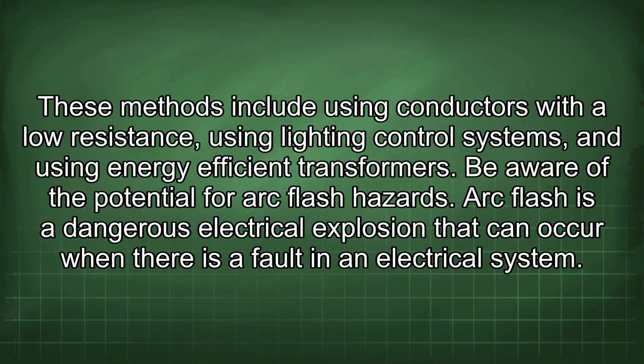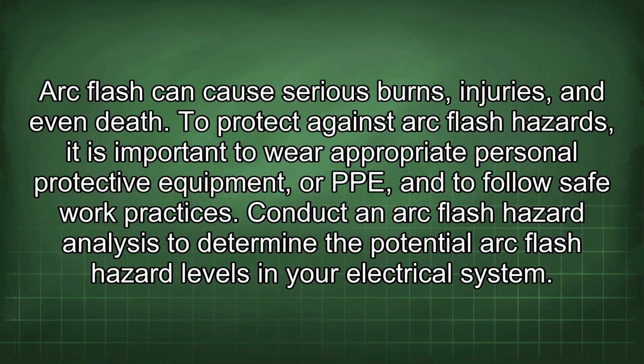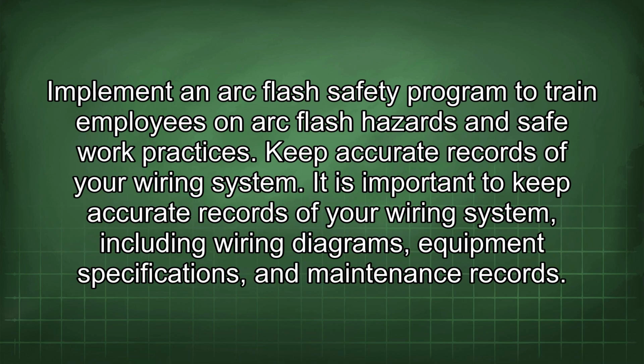Be aware of the potential for arc flash hazards. Arc flash is a dangerous electrical explosion that can occur when there is a fault in an electrical system. Arc flash can cause serious burns, injuries, and even death. To protect against arc flash hazards, it is important to wear appropriate personal protective equipment, or PPE, and to follow safe work practices. Conduct an arc flash hazard analysis to determine the potential arc flash hazard levels in your electrical system. Implement an arc flash safety program to train employees on arc flash hazards and safe work practices.